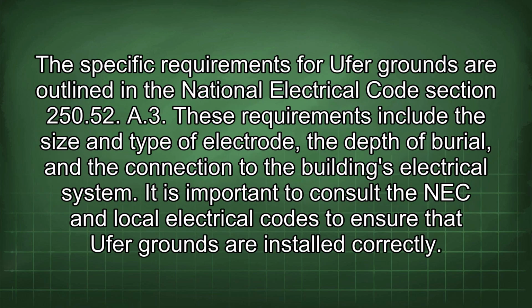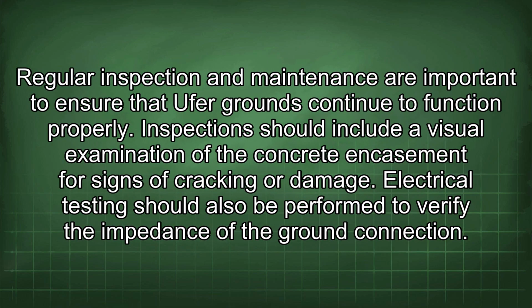The specific requirements for Ufer grounds are outlined in the National Electrical Code Section 250.52(A)(3). These requirements include the size and type of electrode, the depth of burial, and the connection to the building's electrical system. It is important to consult the NEC and local electrical codes to ensure that Ufer grounds are installed correctly. Regular inspection and maintenance are important to ensure that Ufer grounds continue to function properly.